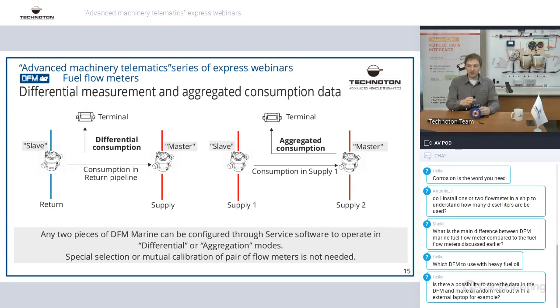So configuring one flow meter on one line as a master and another flow meter on the other line as a slave, we can set settings inside of the master to calculate not the difference, not deducting fuel in the return line from the supply line, but adding the fuel in the other line, and have the total fuel dispensed from the tank. Hope that's clear. If not, please drop us a message or get in contact with our sales manager. But from my point of view, it's pretty simple. Master and slave communicate with each other, either deducting the flow rate of one line from another, or just summing them.